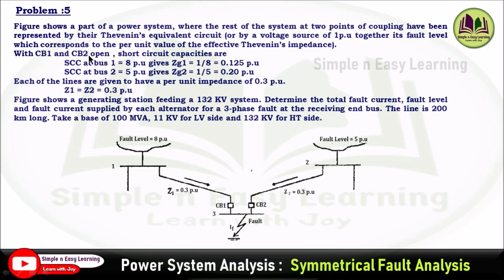With circuit breaker 1 and circuit breaker 2 open, the short circuit capacities are: SCC at bus 1 is 8 per unit. Since the per unit impedance equals 1 divided by the short circuit capacity, Zg1 = 1/8 = 0.125 per unit. The short circuit capacity at bus 2 is 5 per unit, giving Zg2 = 1/5 = 0.20 per unit.